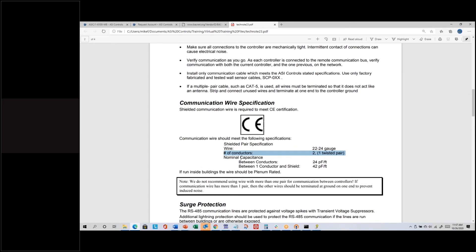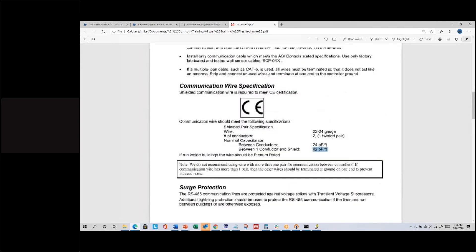You want to make sure it's a single twisted pair for best results. Communication wire should also have a capacitance specification. For shielded wire, you should have two capacitance numbers: between the conductors (plus and minus), lower is better, no higher than 24 picofarads per foot; and between either conductor and the shield wire, again lower is better, at 42 picofarads per foot or less. That's usually referred to as mid-cap wire. LonWorks communication requires low-cap wire at 12.5 picofarads per foot between conductors, which works fine since lower is better.